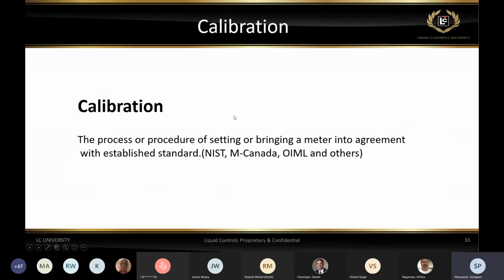Again, I'll just repeat the definition of calibration. It's a process or procedure of setting or bringing a meter into agreement with whatever standard we need to use. The combination of the meter, gear plate, counter, and gear ratio puts you in a ballpark, puts you where you need to be in order to calibrate or do fine tuning, to make the meter repeatable and accurate.